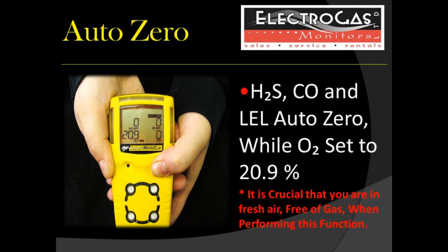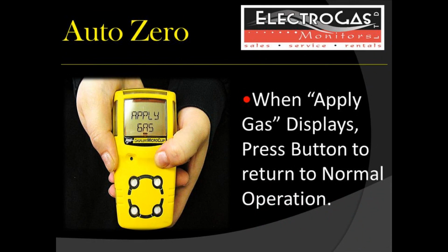It is critical that you are in fresh air, free of gas and toxins when performing this function. When apply gas displays, you may press the blue button to return to normal operation. If you do not and the calibration sequence times out, the next time the unit is turned on, it will display last attempted cal failed.